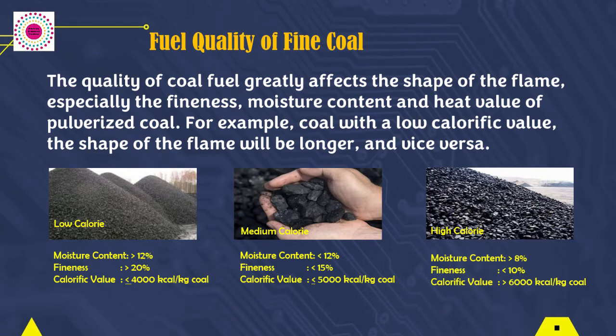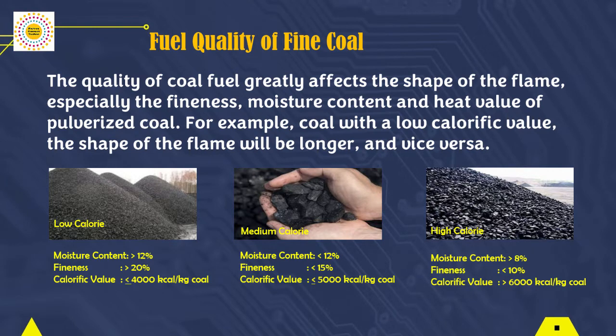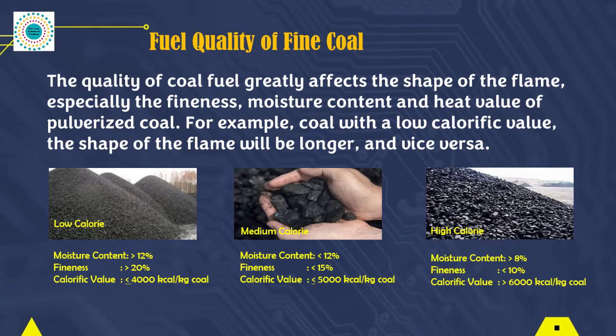For example, coal with a low calorific value will produce a longer flame shape, and vice versa. Because low-calorie coal has a high moisture content and high volatile matter, it should not be too finely ground. This will result in a long flame shape and the potential for a second combustion to occur in the kiln.